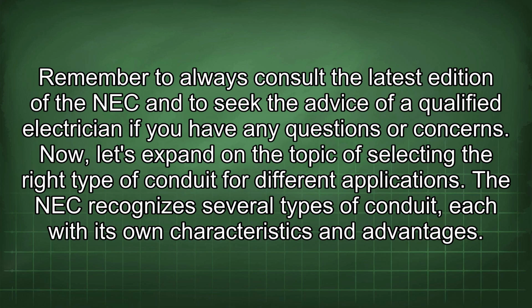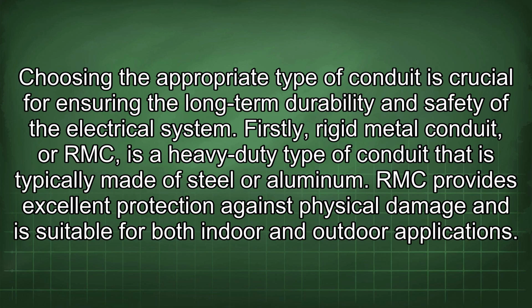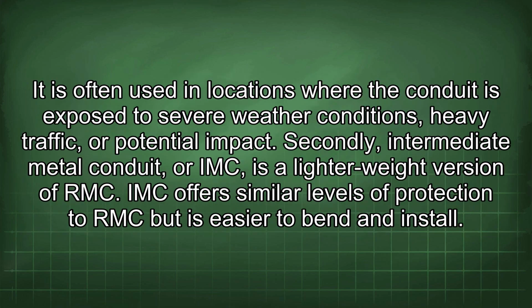Now let's expand on the topic of selecting the right type of conduit for different applications. The NEC recognizes several types of conduit, each with its own characteristics and advantages. Choosing the appropriate type of conduit is crucial for ensuring the long-term durability and safety of the electrical system. Firstly, rigid metal conduit, or RMC, is a heavy-duty type of conduit that is typically made of steel or aluminum. RMC provides excellent protection against physical damage and is suitable for both indoor and outdoor applications. It is often used in locations where the conduit is exposed to severe weather conditions, heavy traffic, or potential impact.